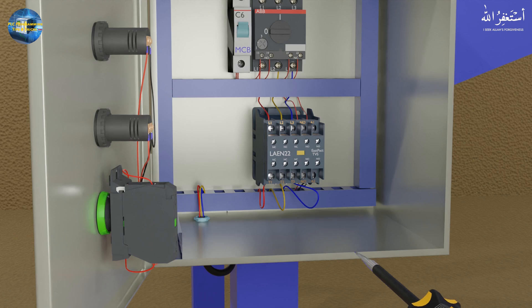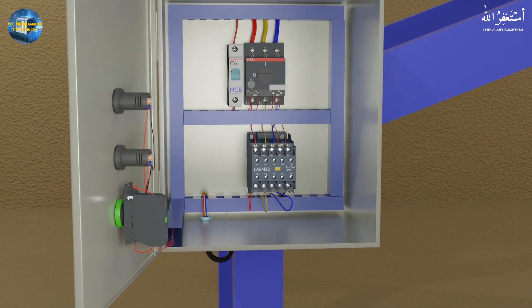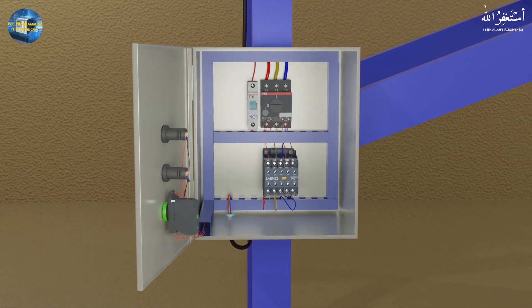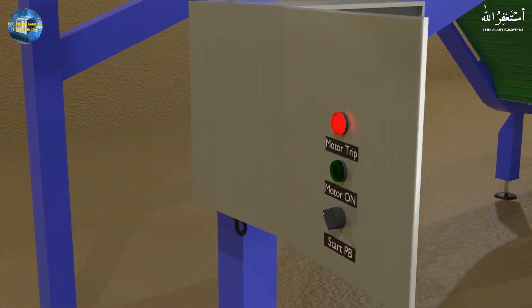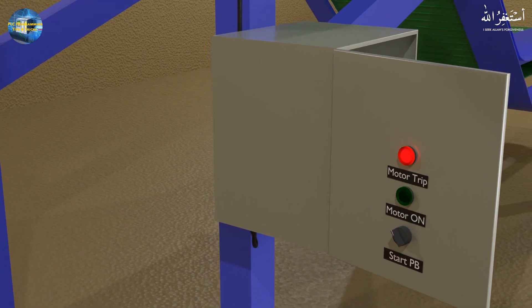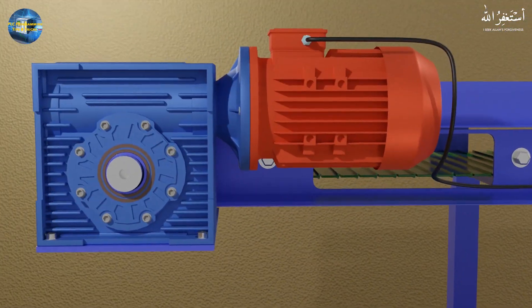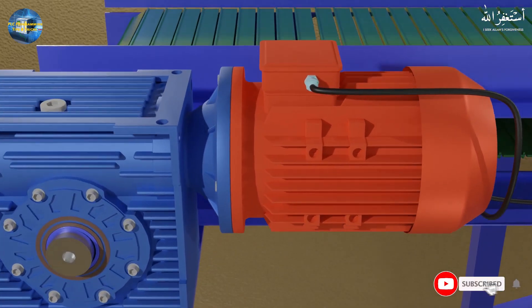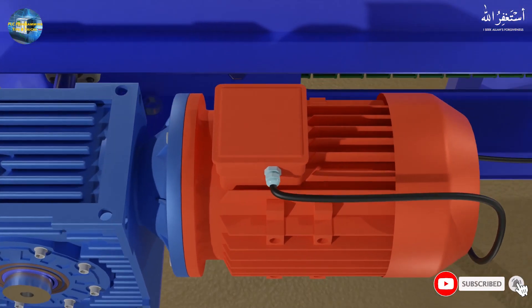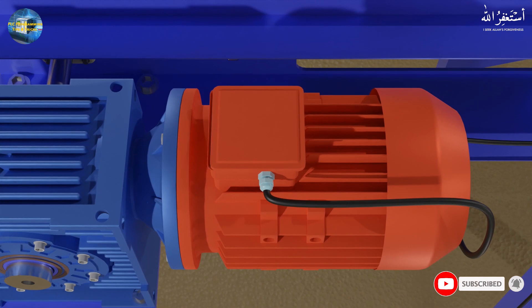If there is no loose connection in the motor circuit, we can move forward and check for any physical damage to the motor cable, which can cause a short circuit in the cable. After checking the motor cable, next we can go to the motor and check the wire connections in the junction box.